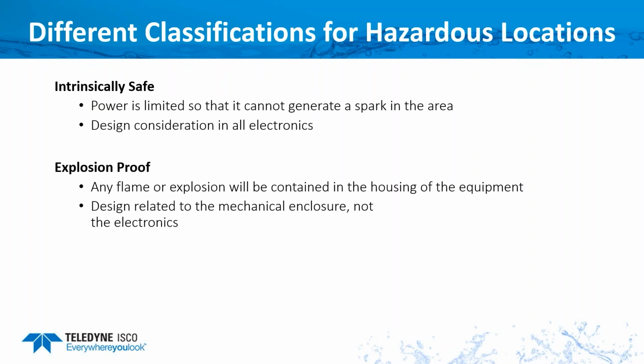Now the other category is explosion proof. What that is, is that any flame or explosion will be contained in a housing of the equipment. The design relates to the mechanical enclosure, not the electronics. So what you're going to see is a big steel or stainless steel enclosure that, if there was an explosion, would actually contain it. So it doesn't stop it, but it contains it from spreading elsewhere. But what I'm concerned with today is the intrinsically safe part of it.